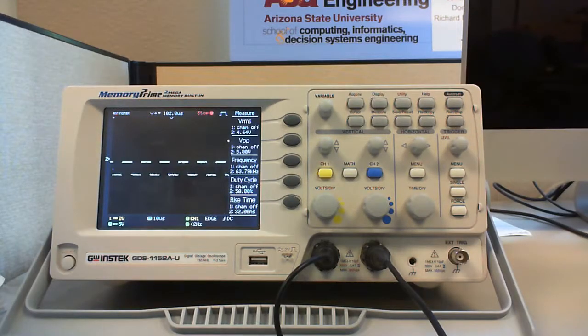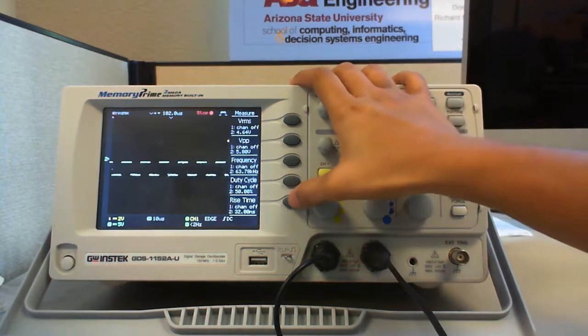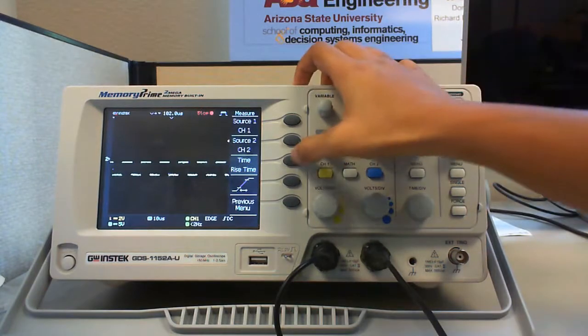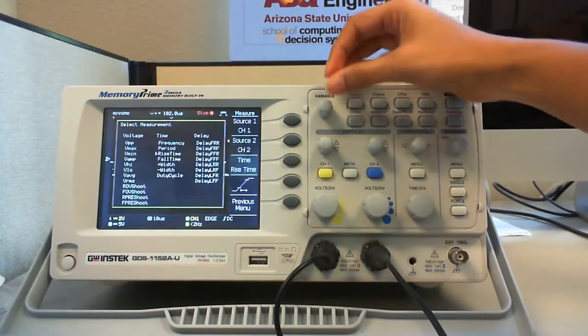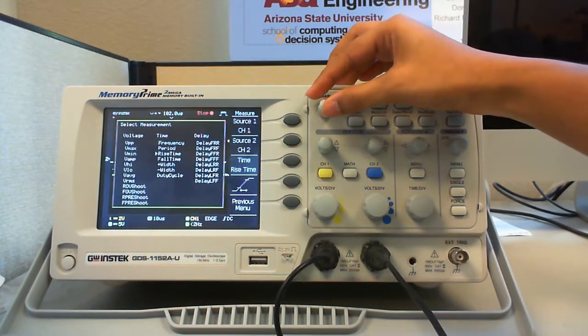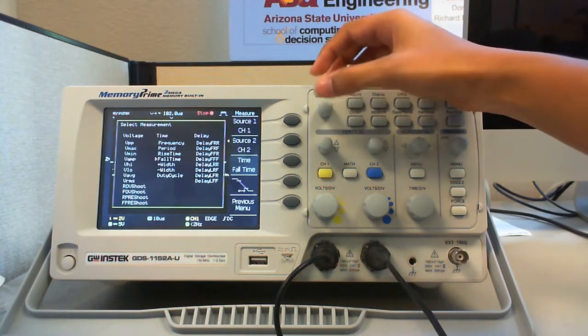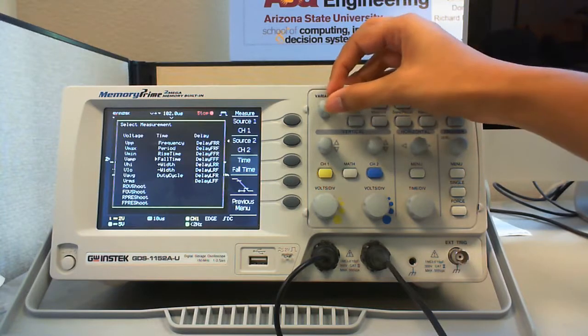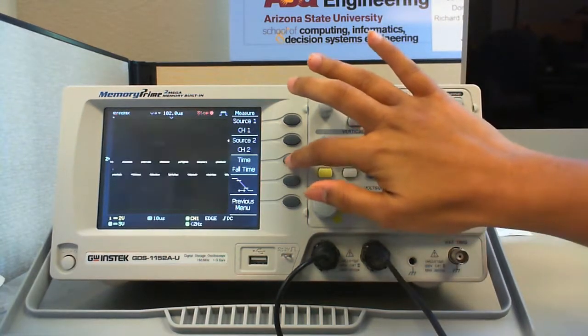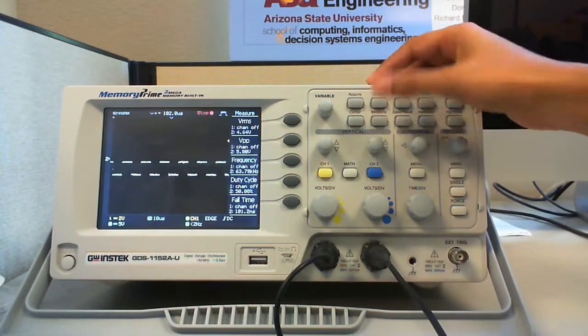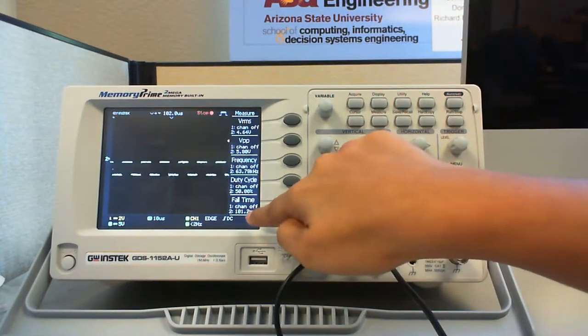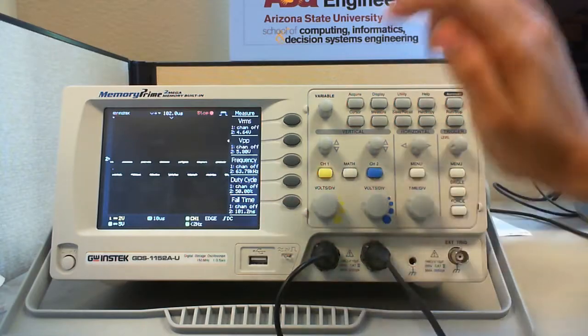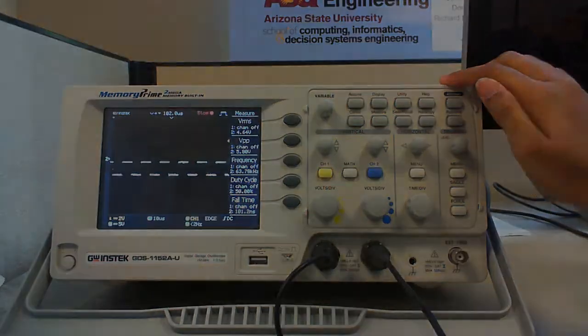If you want to change any of the parameters here, you can select any of the options and rotate the variable control knob to the desired parameter. If you want to check the fall time now, select the fall time by rotating the variable control knob and press measure. The fall time of the signal that is 101.2 nanoseconds is displayed on the screen.